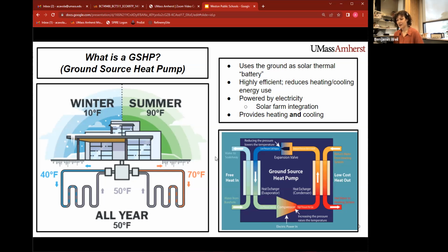So how does this work? Water circulates through pipes in a geoexchange field. A heat pump in the building uses the compression cycle to exchange heat between this water and the building's heating and cooling supply water. What makes this different from other heating and cooling systems?